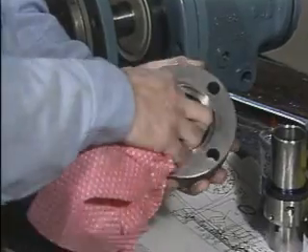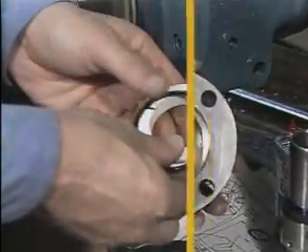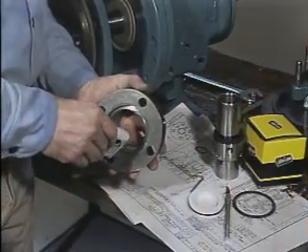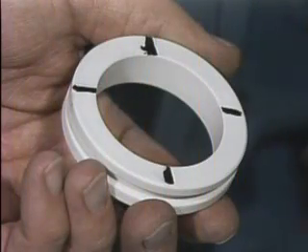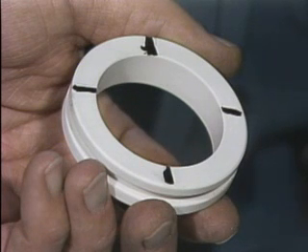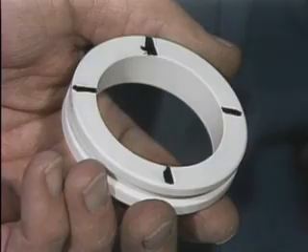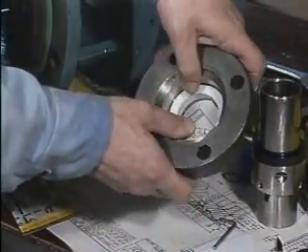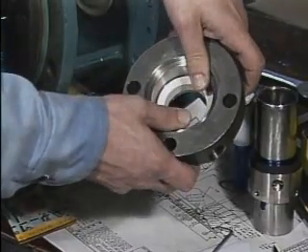First, the gland plate is wiped clean with a cloth. Then the O-ring is installed onto the mating ring. Next, the gland plate is lubricated to make the mating ring installation easier. The mating ring has a polished side and an unpolished side. Most manufacturers mark the unpolished side of the ring to distinguish it from the polished one. The mating ring is inserted into the gland plate so that the unpolished side goes in first.